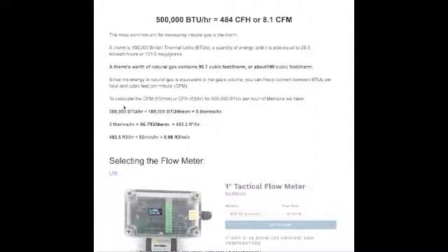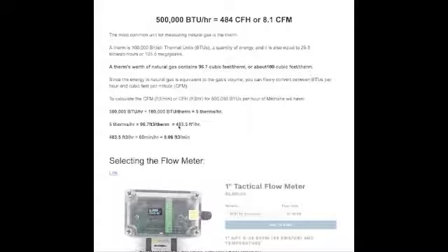Let's get to the main calculation. 500,000 BTUs per hour divided by 100,000 BTU per therm equals 5 therms per hour. 5 therms per hour times 96.7 cubic feet per therm equals 483.5 cubic feet per hour.